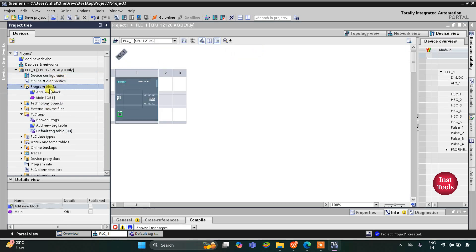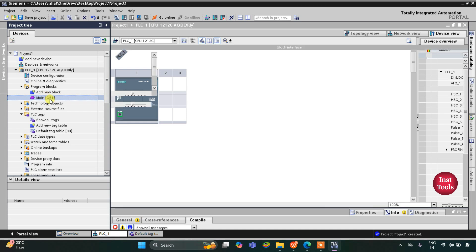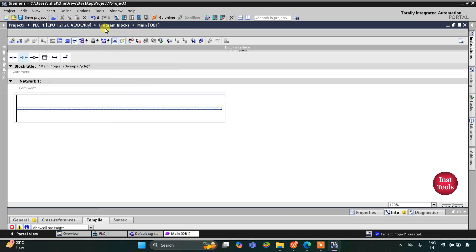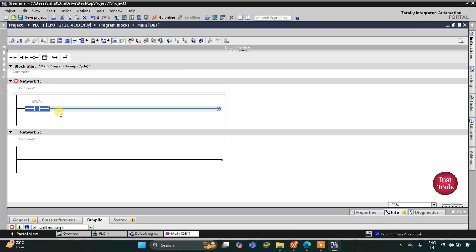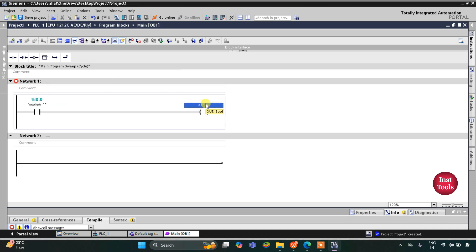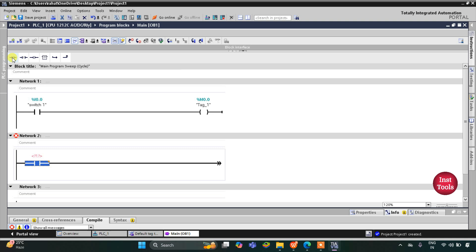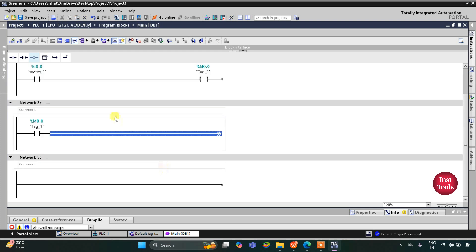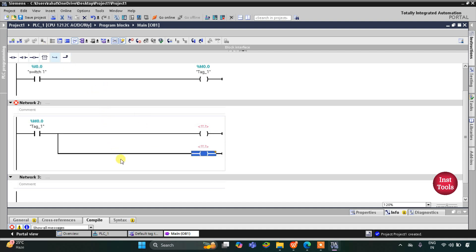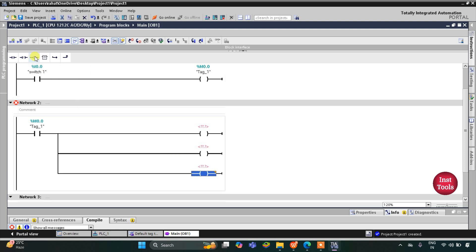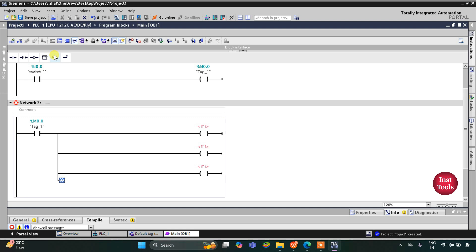I will minimize this and go to program blocks and then main OB1. Here we will draw the ladder diagram. Firstly I will insert a normally open contact and a coil. This normally open contact will be switch one and this coil will be the memory bit, so I will assign address M0.0 to it. Then I will use M0.0 here as a normally open contact to turn on the motors. I will insert coils — coil one, then open branch, one more coil, open branch, then another coil, open branch, and a final coil.